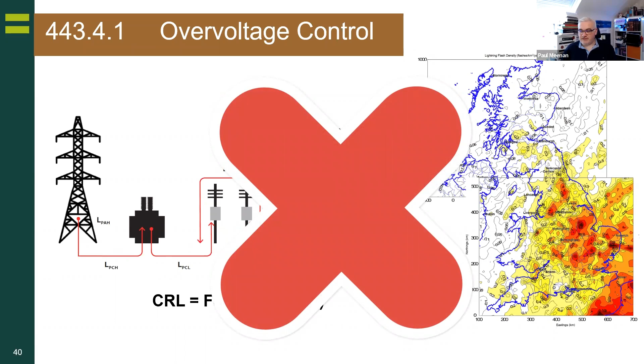And now there is, in overvoltage control, we have protection against transient overvoltages shall be provided where consequences by the overvoltage could result in serious injury to or loss of human life, failure of a safety service as defined in Part 2, and significant financial or data loss. Now, to me, that's emergency lighting, that's fire alarms, that's pretty much in most commercial buildings. Safety services, what that is in the eye of the duty holder and the responsible person. But it then says for all other cases, protection against transients shall be provided unless the owner declares it not required due to any loss or damage being tolerable and they accept the risk of damage. So there is still a caveat to not do it.